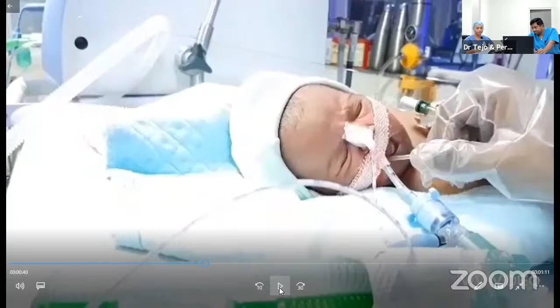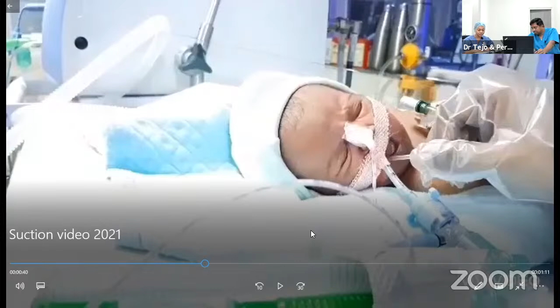The suction pressure should be fixed at 80 to 100 mm of Hg. And the suction pressure for a small baby should be slightly lower, and for a term baby, or if the baby is having thick secretions, then it should be slightly higher. That means around 100 pressure. An important thing to note is the tip or the key part which you are inserting into the ET tube. It should not be touched anywhere, or exposed, till introducing into the ET tube. As in ANTT techniques, as we are learning, this should be done. And before introducing, the length of the suction catheter has to be measured.